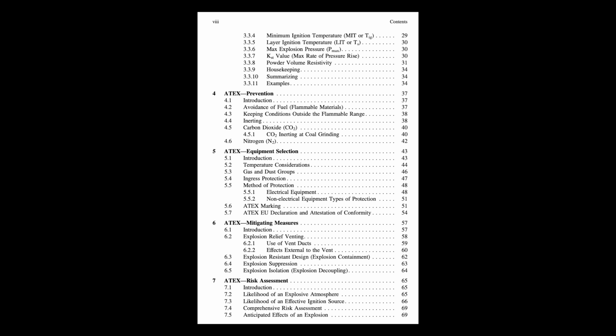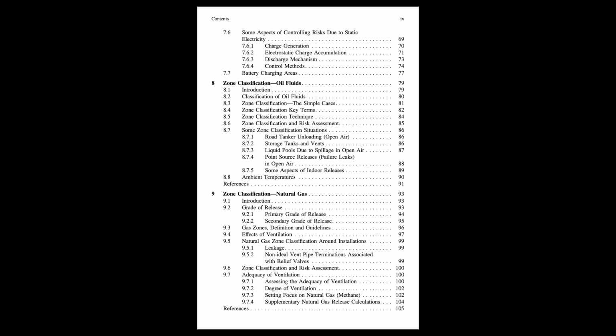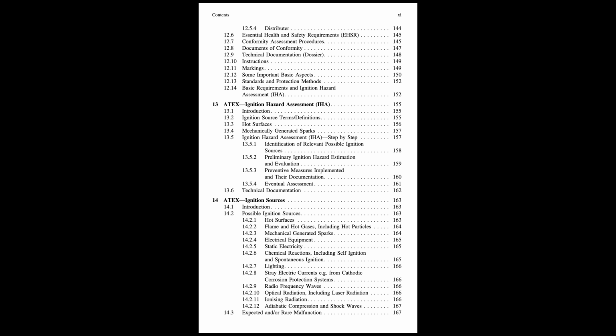So you categorize dusts based on this? Yes. The guide mentions categories like conductive, dissipative, and non-conductive based on resistivity ranges. This helps determine appropriate handling procedures and even links to the required IP rating, dust tightness, for electrical enclosures in the area. Interestingly, it notes that truly conductive powders are rare because even metal powders often have insulating oxide layers.